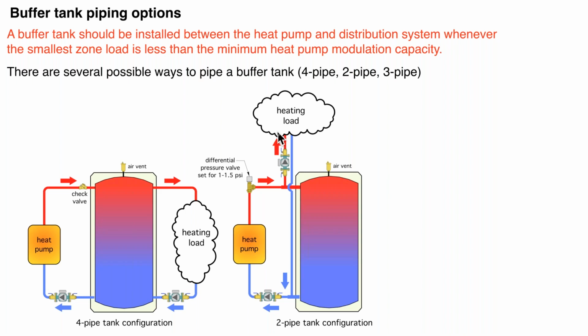All right. The other thing that happens with a 2-pipe buffer tank is, when the load and the heat pump are operating simultaneously, the only flow that's actually going through the tank is the difference in flow rate between the heat source flow rate and the load flow rate. So let's say the heat pump was operating at 12 gallons per minute and the load was taking 8 gallons per minute. The difference would be 4, and that's what's going into the buffer tank. Now, why does that matter?